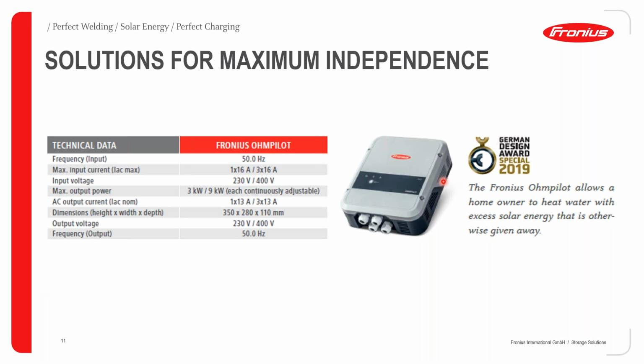Okay, the Ohmpilot comes as a single device that can be either wired as single phase or 3-phase. It takes a maximum input current of 16 amps on the single phase, or on the 3-phase, 3 times 16 amps. Input voltage 230 volts for single phase and 400 volts for 3-phase. Maximum output power for single phase will be 3 kilowatts, and for 3-phase will be 9 kilowatts. Okay, again, you can also have a read through the other stats, but we will further elaborate on the Ohmpilot a bit later on in today's presentation.